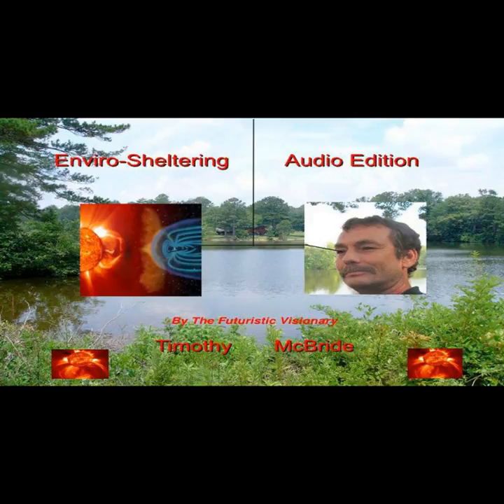In a thermal siphoning solar hot water collector system, the storage tank located above the collector receives heated water from the top of the collector into the top of the storage tank. Colder water from the bottom of the storage tank is drawn into the lower entry of the solar collector to replace the heated water that was thermal-siphoned upward. The thermal siphoning system is more costly and complex than the batch system. In this area, it is best to use an indirect system employing a heat exchanger, in which case antifreeze can be used to eliminate freeze-ups.